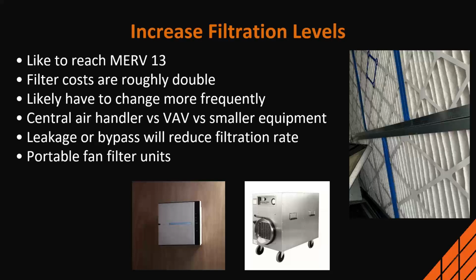Our larger equipment is going to be able to handle this better. So if we have a bunch of little fan coils or heat pumps or things like that, or VAV boxes, we're not going to be able to get too far on the filters. A lot of those are going to have a 4 or 6 MERV rating on them, especially VAV, and you might be able to get to 8 to 11. If we get above 5 tons or so, we'll probably get to 11 or 12. And if we get 10 tons and up, we're probably going to be able to get to 13. But basically, you need to look at each piece of equipment, the size of the equipment, the amount of ductwork, the size of the motors, and things like that, and figure out how far you can go.